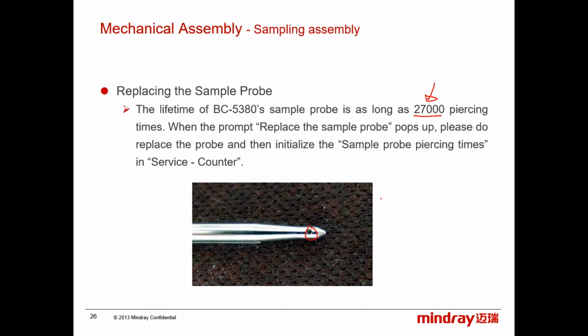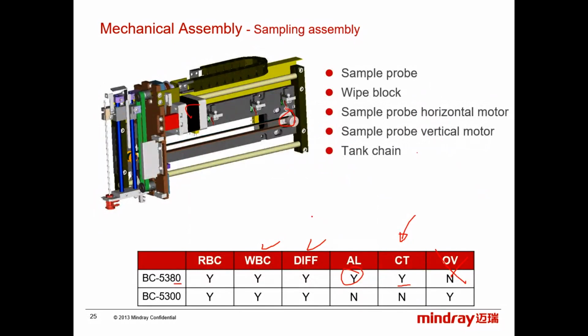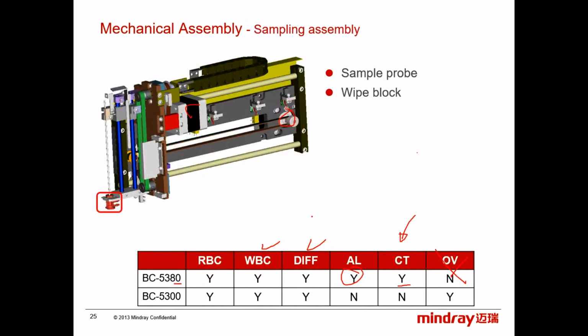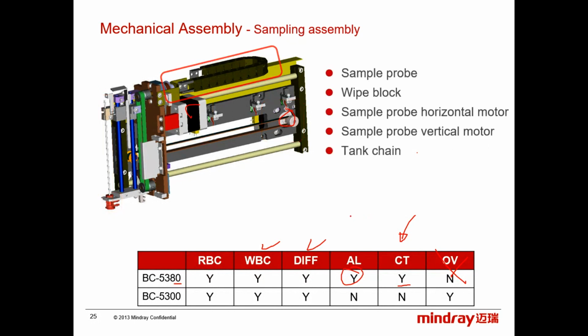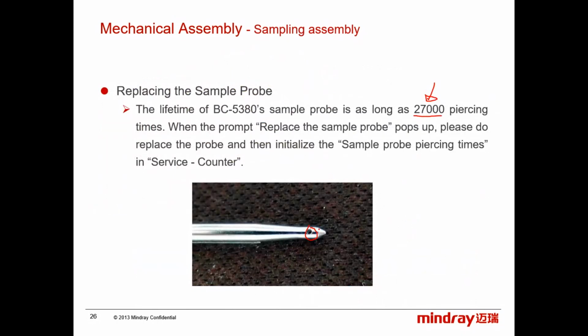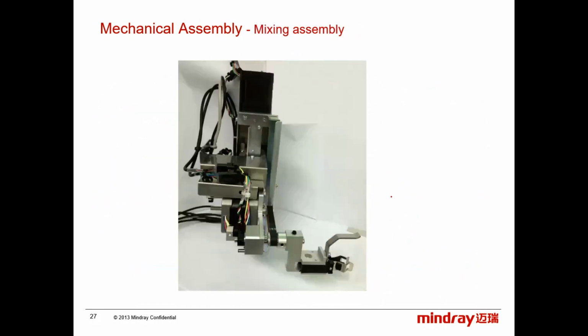This is very important, guys, because you can initialize the counter without replacing the probe, but it is not recommended. Because with time you will lose this cap pierce function. It will lose the ability to pierce the tube. So you will get very frequent partial aspiration errors because of this. So make sure to replace in time.